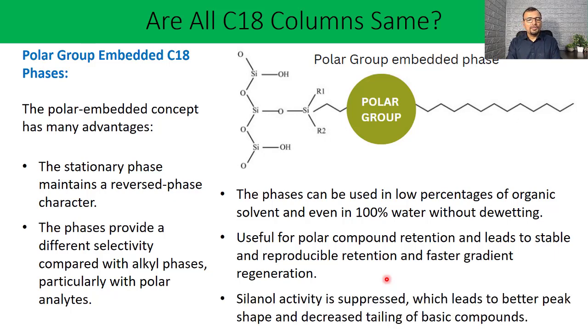Let us discuss the last important advantage. The silanol activity is suppressed, which leads to better peak shape and decreased tailing of basic compounds. This is a very important characteristic of polar embedded groups. Silanol activity gets minimized, and we all know because of the silanol secondary effect, most of the time basic compounds have a lot of tailing issues.